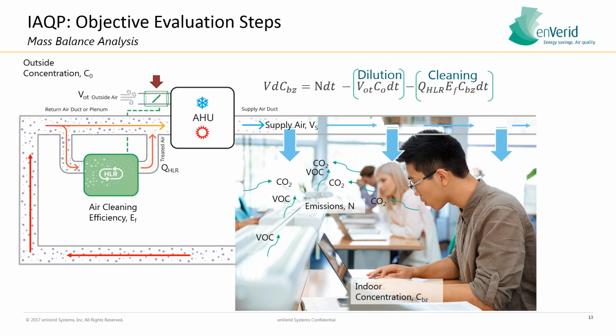It's very simple, but basically, the first two parts of that equation, Ndt and the dilution component, are essentially what you're doing with the ventilation rate procedure. ASHRAE knows emission rates within space types of CO2 and VOCs based on occupancy and the type of space that it is, based on decades of studies that they've done on emission rates of furniture and human emissions of CO2. What we do right now is we know that emission rate, and we bring in a certain volume of outside air to dilute those contaminants.